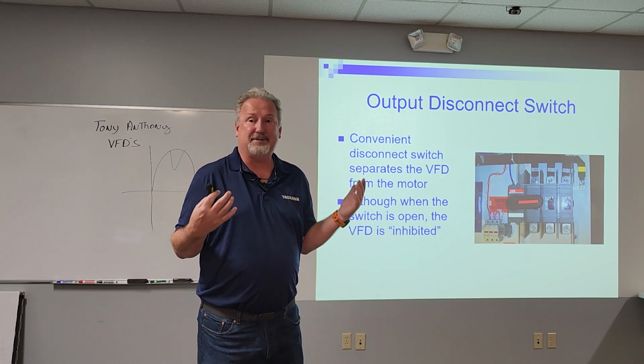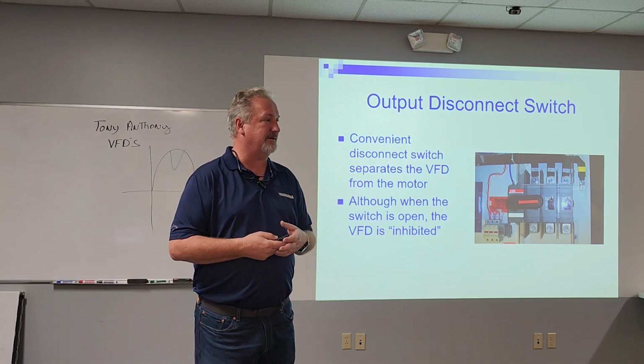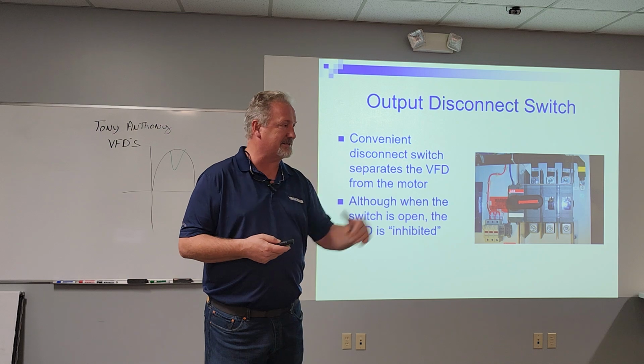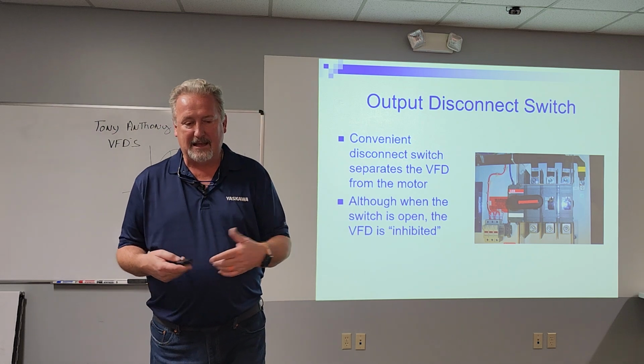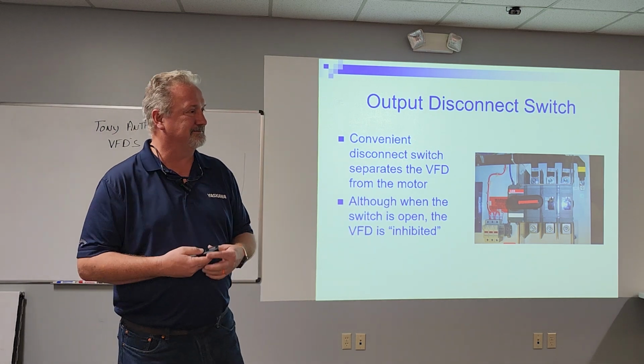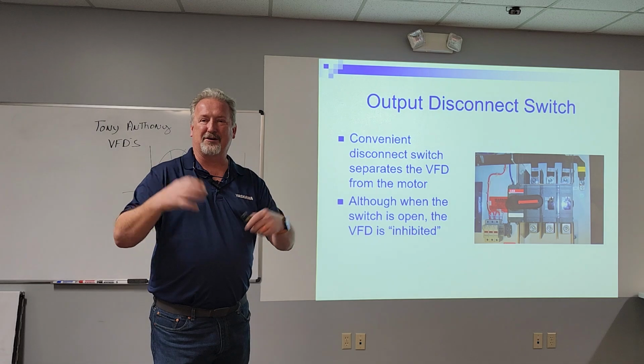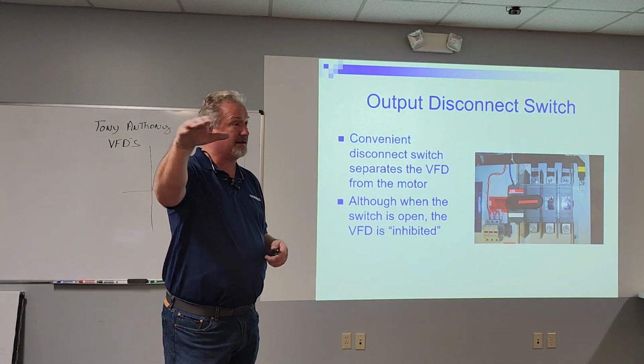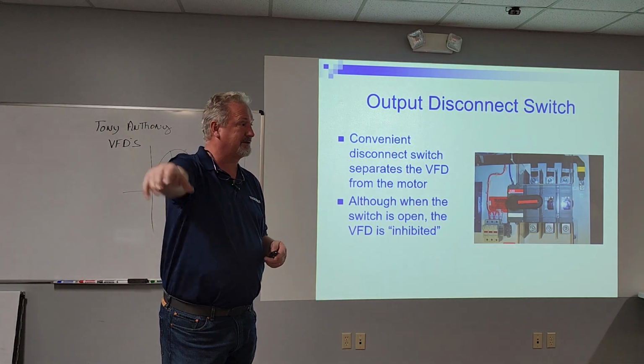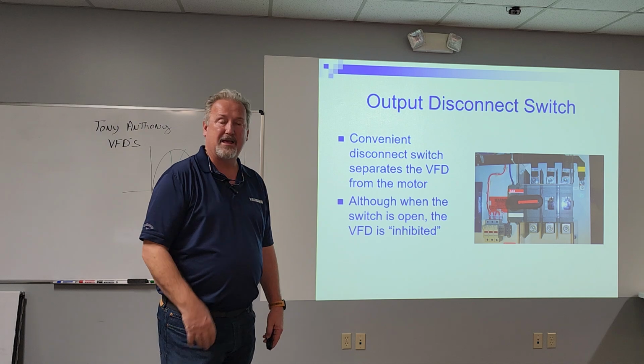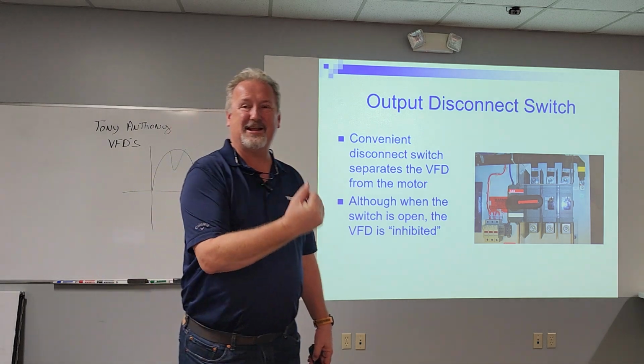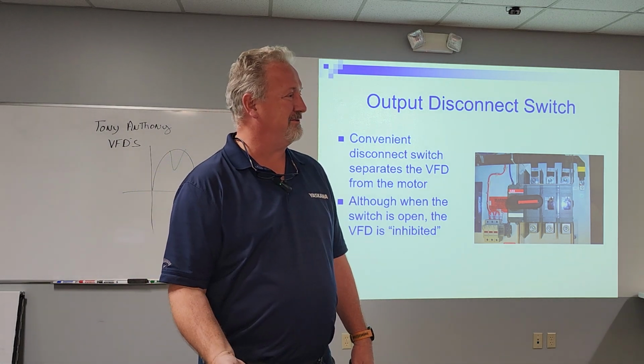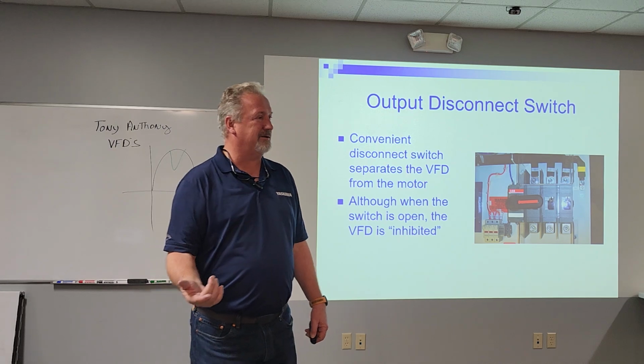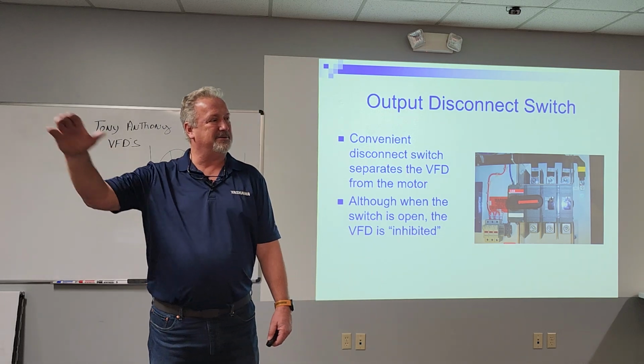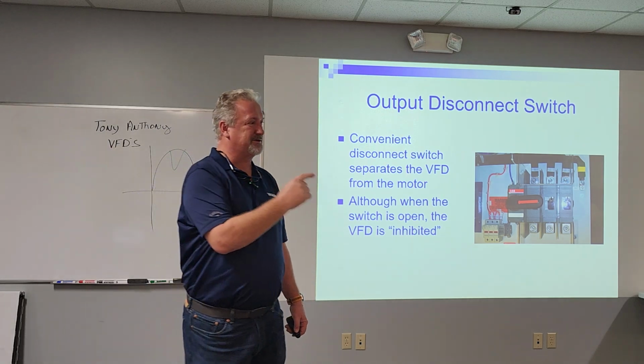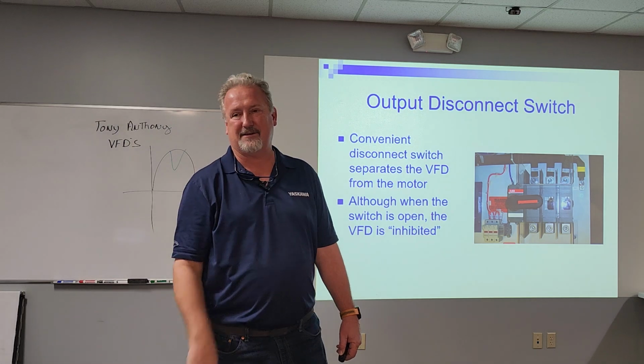The drive's just sitting there going, hey, I got really lightly loaded all of a sudden, unless you've set it up to sense that, which in most cases we don't. It's like, hey, my load's low. Then you do your work, you close that disconnect, and the drive's been sitting out there putting out 45 hertz the whole time, just not going anywhere. Now you close that disconnect because you finished your work on that motor. Instead of ramping it up slowly like we do with a drive, you're trying to take that motor from 0 to 45 hertz instantaneously.